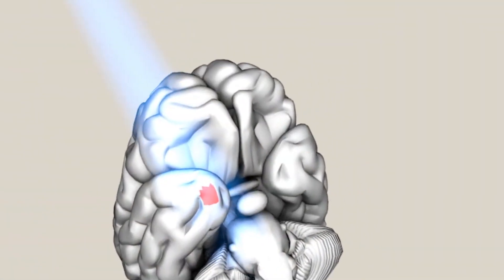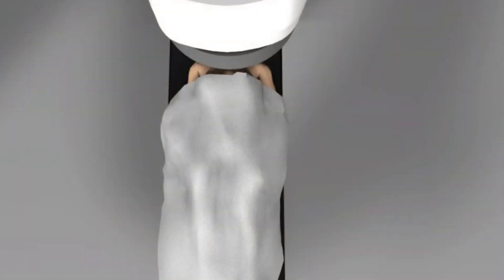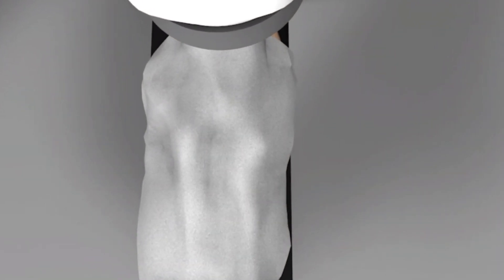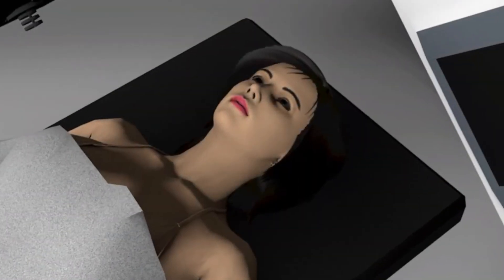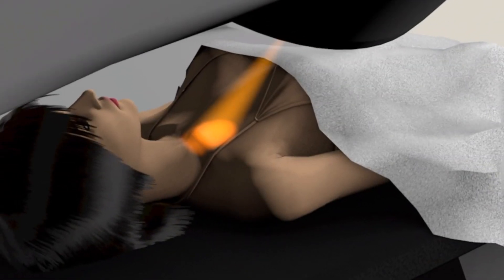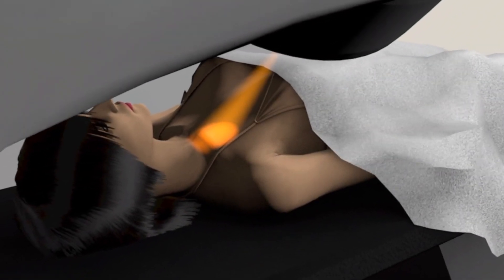Setting the position of the deflector magnets takes about 8 seconds. If the radiation type and power parameters were changed during this time and the cursor was set to the final position, the system would not detect the change. Additionally, dividing by the value of the radiation led in some cases to a division-by-zero error, with a corresponding increase in the radiation value to the maximum possible.